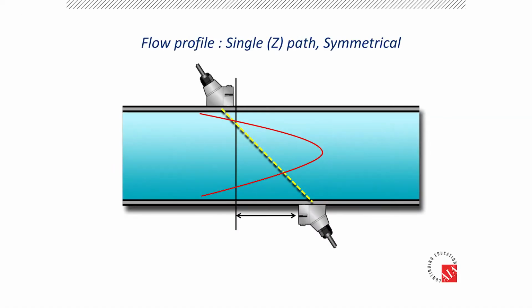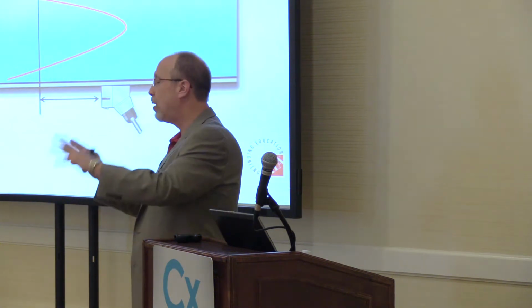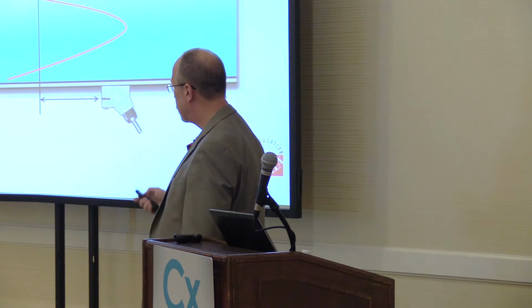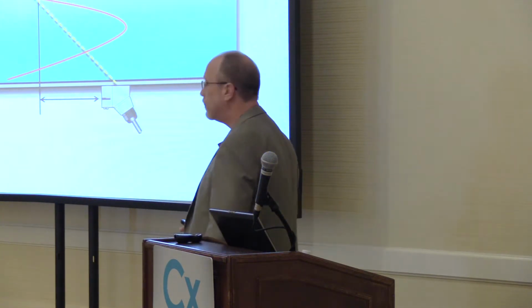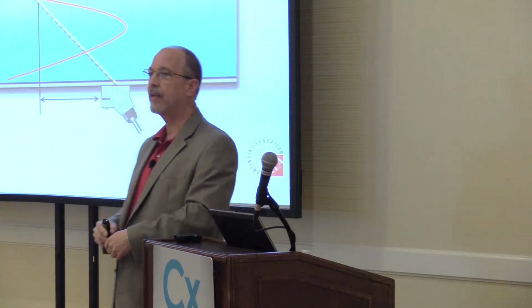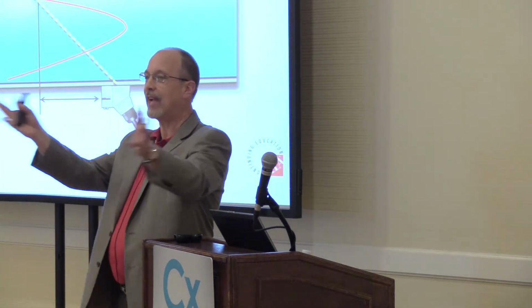Well, I just happen to have a flow profile. And as we mentioned before, it's all a math equation. So before this guy even goes on the pipe, I know where the transducers go. So I've got this 10-inch carbon steel pipe. I program the meter with the pipe outside diameter, the pipe wall thickness, and the pipe process liquid, and it says move your sensors apart this distance. We turn it on, boom. They all connect. Perfect. The device is 1% of rate, within the factory specified.